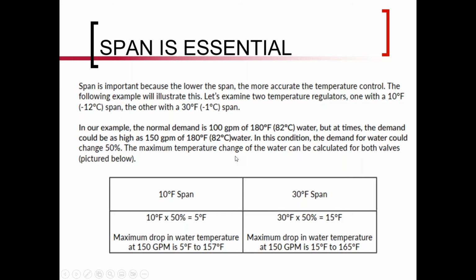So in this example, real quick, we'll assume that one product has a 10-degree span. And that again means set at 150 I used earlier. Well, this example uses 180, so I apologize for that. But the valve should be completely open to close between 175 and 185, a 10-degree span. Another unit may have a 30-degree span. So in this example, you're going along at 100 GPM at 180 degrees F, and it's holding it there because the flow is pretty consistent. So it's a pretty benign heating application.